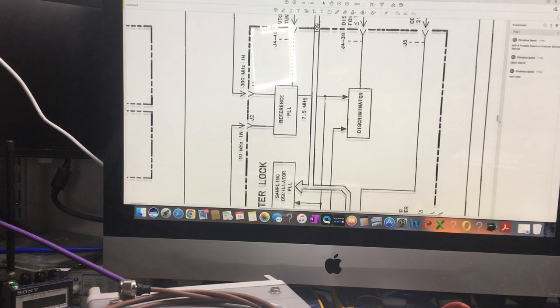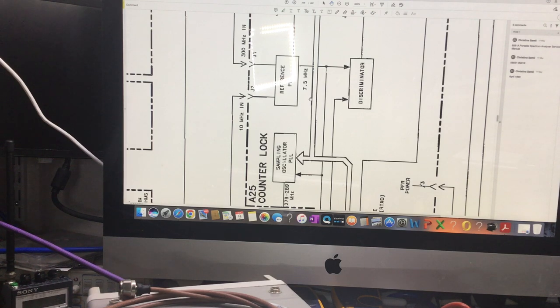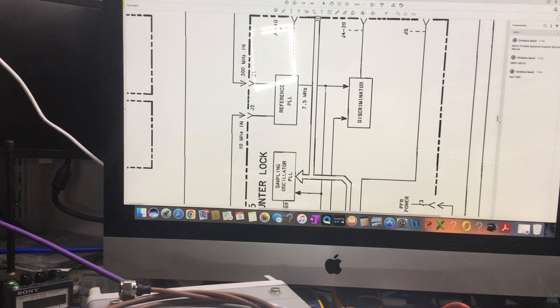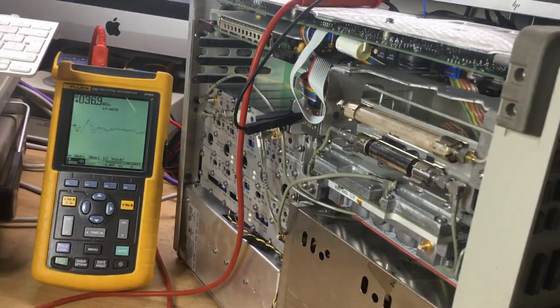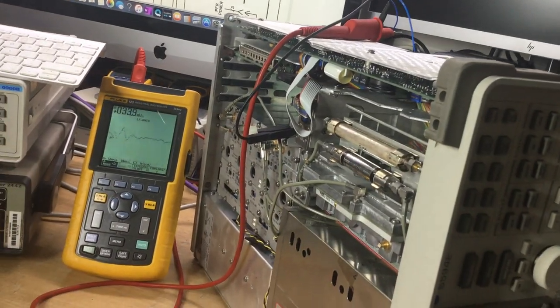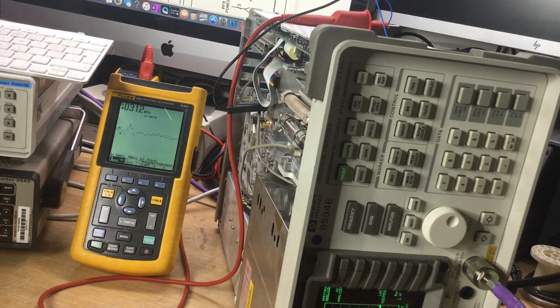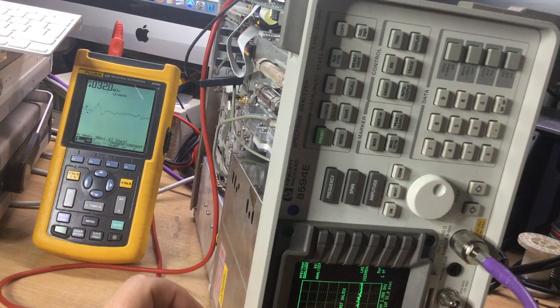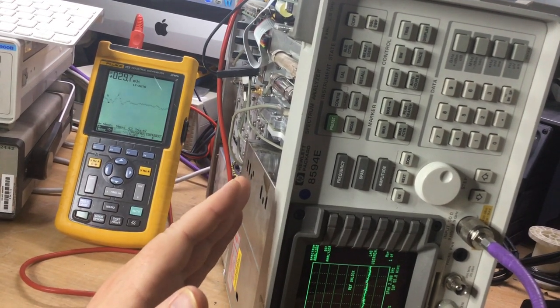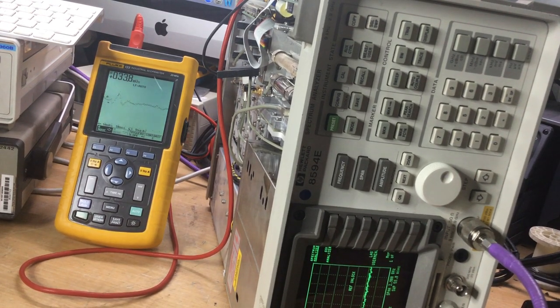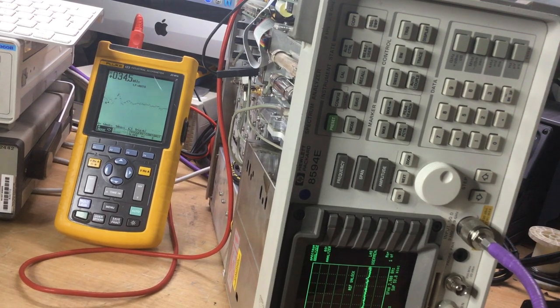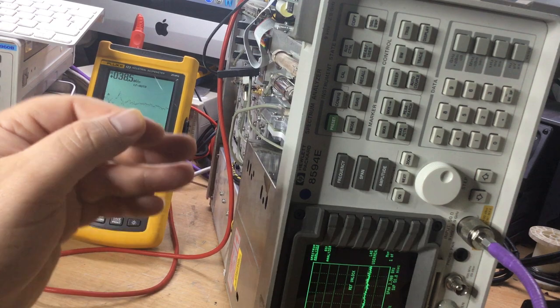So unless we can get spares for that entire block in the instrument, that's one of those major modules in the bottom of the instrument, and it's quite an involved process replacing that if we had spares. Unfortunately I don't have any spare parts for this particular spectrum analyzer, because it's what they call the low-cost spectrum analyzer, and these models have different innards to the other models of spectrum analyzers. I have spares for the higher level spectrum analyzers, such as the 8560 series, which are the higher spec models, not the low cost spectrum analyzer.